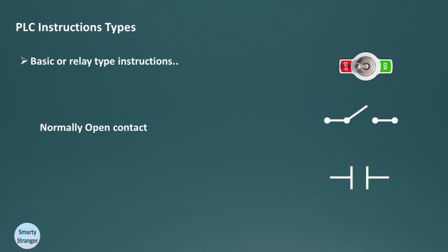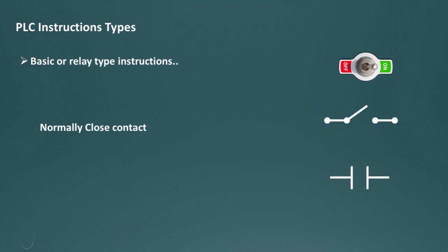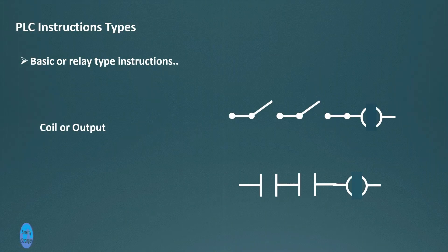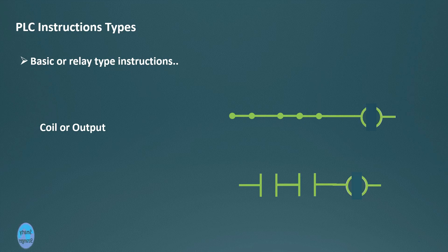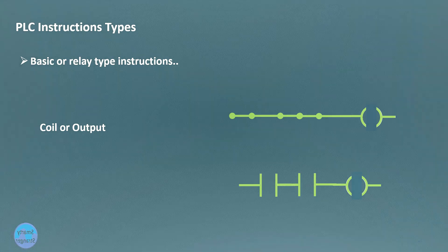When the input is de-energized or low, the normally open contact becomes open again. Similarly, a normally closed contact is like a closed switch — when its corresponding physical input is energized or high, the normally closed contact becomes open, and when the input is de-energized or low it becomes closed again. The third is the output coil: if all conditions in the rung are fulfilled, the corresponding bit in the output data memory is set high and the device is energized.